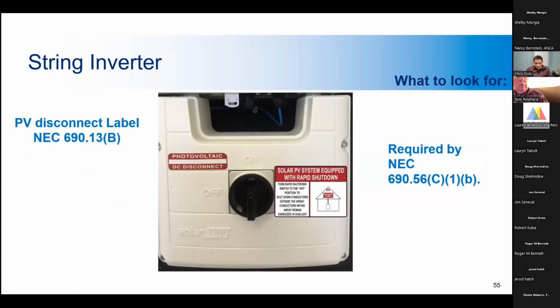And lastly, for string inverters, we'll take a look at the labeling requirements per NEC 690. This inverter right here has a disconnect handle built right into the inverter. It also has to be labeled as a DC PV disconnect, and also that it has a rapid shutdown feature.